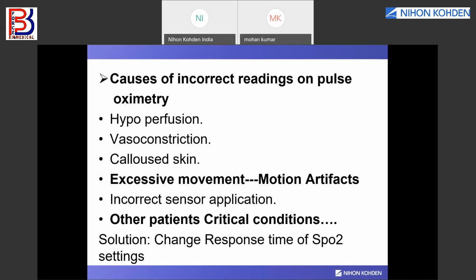Now, the solution to this motion artifact or low perfusion: as we've seen, you can change the site, but if even after changing the site you are not getting proper SpO2, there is a setting in the patient monitor or SpO2 monitor, that is to change the response time. Now you can see in this graph the SpO2 versus time graph. In Nihon Kohden it has 3 selectable ranges: slow response, normal response, and fast response.